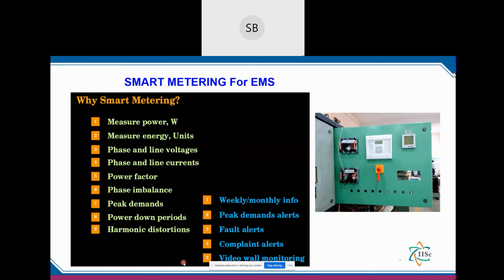Smart metering is basically used to measure power and energy, like earlier meters. Apart from that, we also get information about phase and line voltages, phase and line currents, power factor information, and phase imbalance, which is very important since as I mentioned this is a very old institute without proper planning in many departments. Equipment gets connected without looking into balance, so some phases are more than 80% loaded while others are 20% or less. So we have a lot of phase imbalance across the institute, and smart metering or sensor-based information helps us identify and correct these issues.